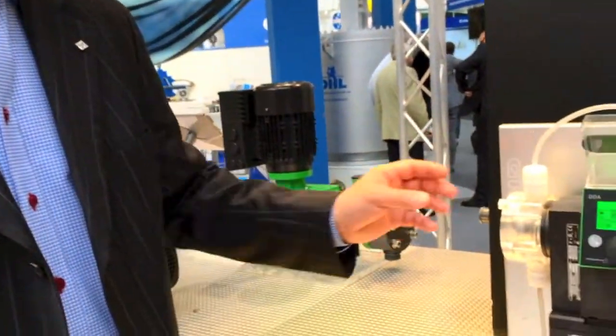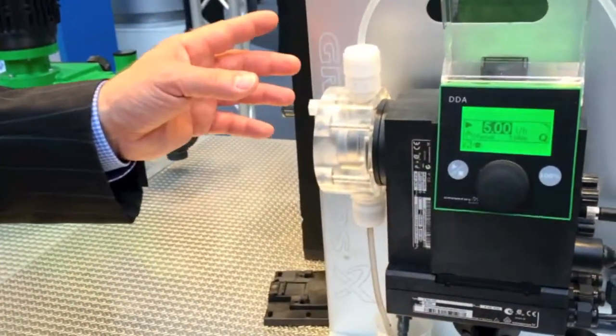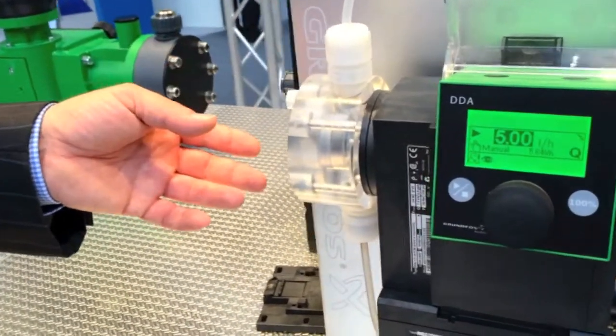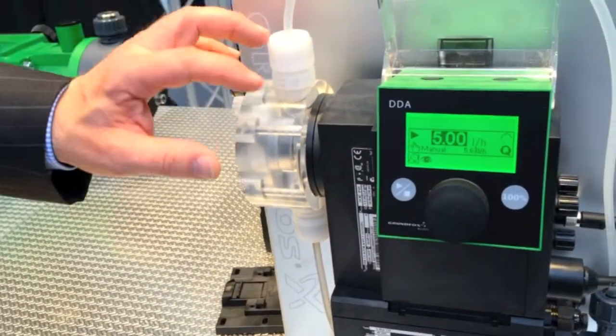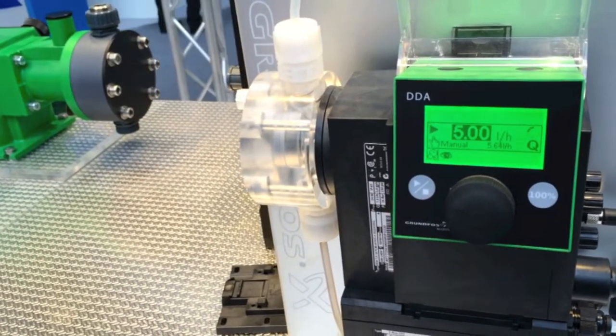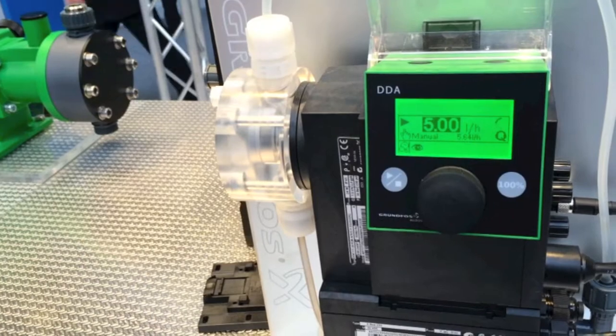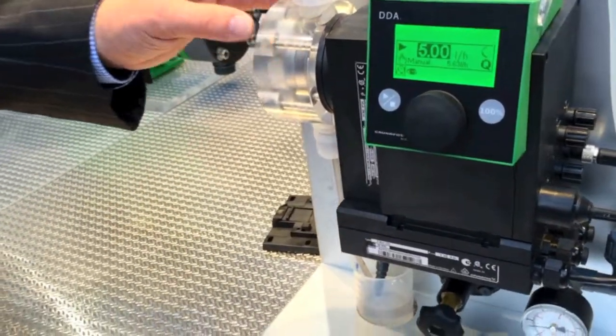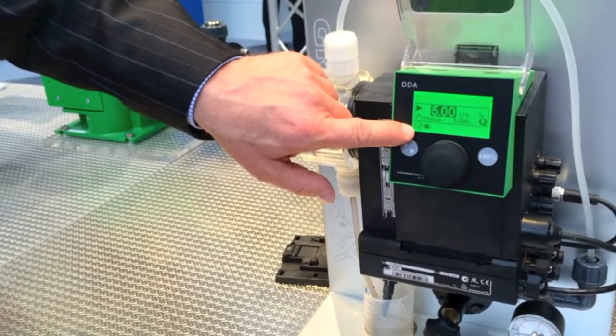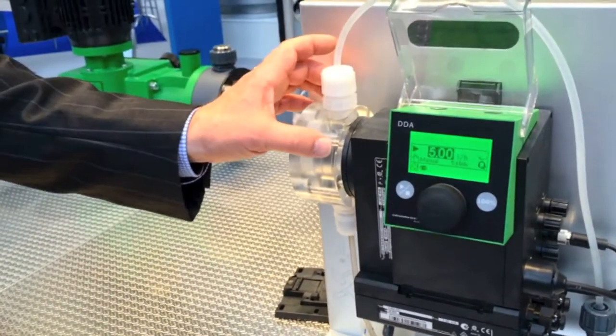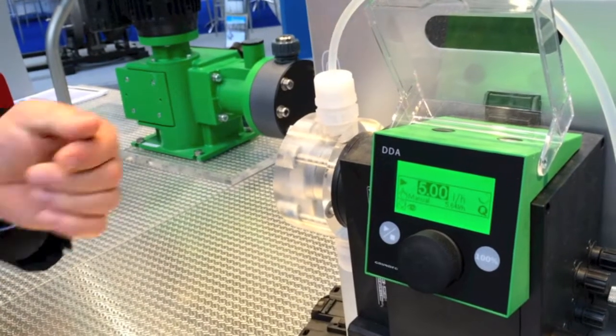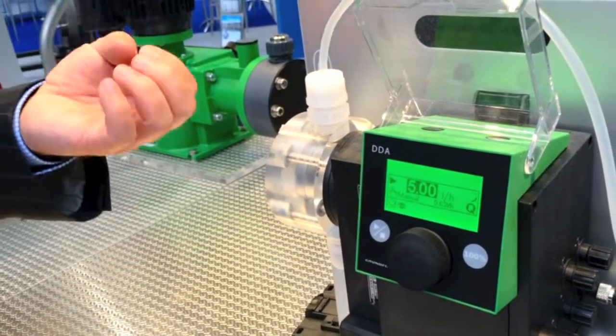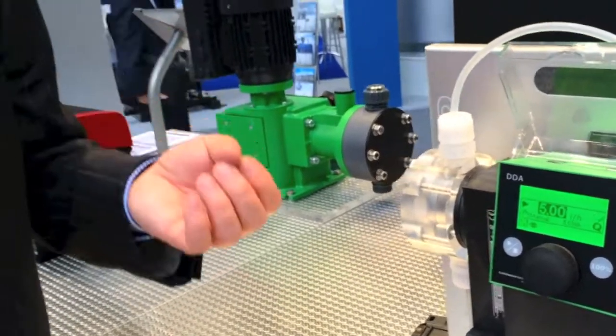The other thing is air handling. If the pump stands at the weekend with gaseous liquids, the dosing head can be blocked full of air bubbles, and if you want to start the pump, it will not start. In our pump, if you activate the aeration functionality, the membrane will vibrate every 20 minutes so the pump gets rid of the air bubbles, and on Monday when you start, the pump is back in operation. The other benefit is our auto flow adapt functionality.